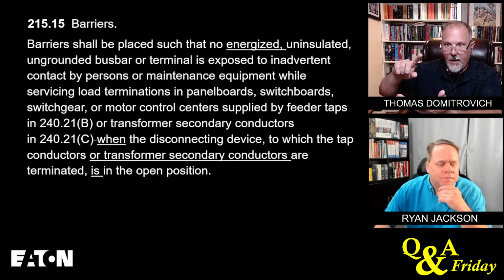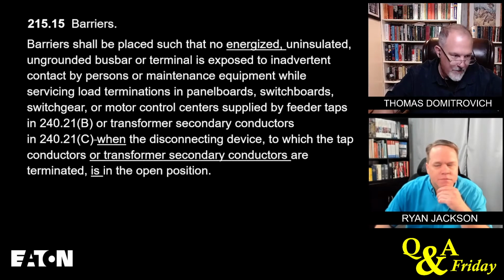Here is my other issue, which is on the same lines as this discussion. When you go to 240, you can see my tap section has seen a lot of wear because I get a lot of questions about taps. Now, if you look at 240.21, 240.20, I got it backwards. Okay, 240.21, the title of that section is location in circuit, right? Mm-hmm. So you have A, branch circuit conductors, and then you have B, feeder taps.